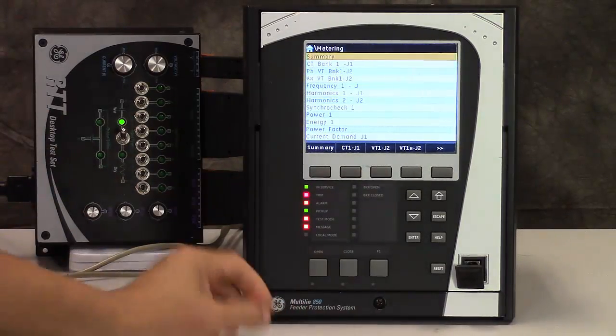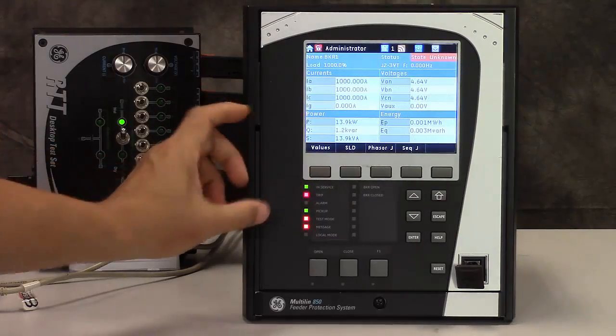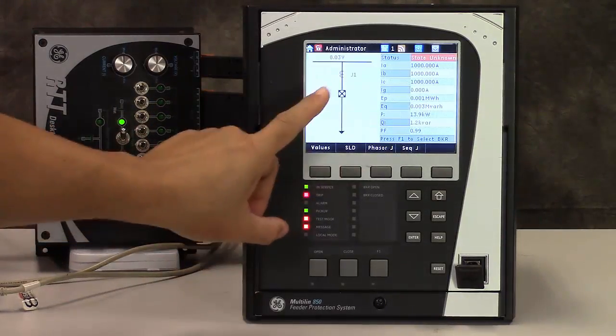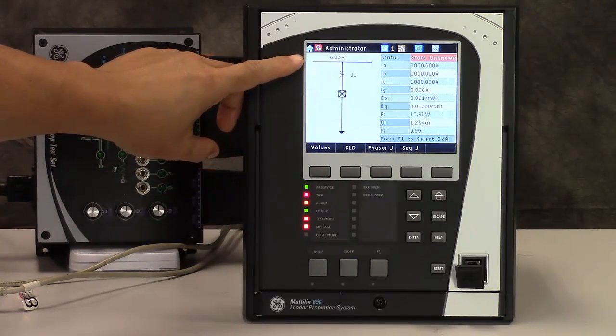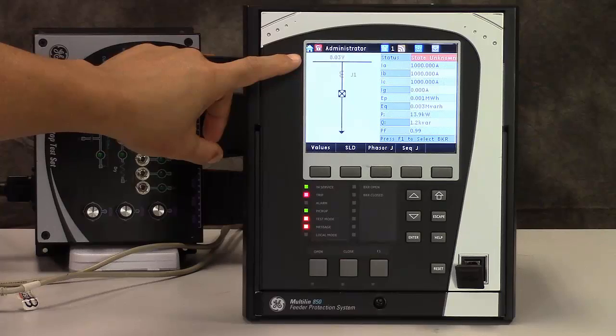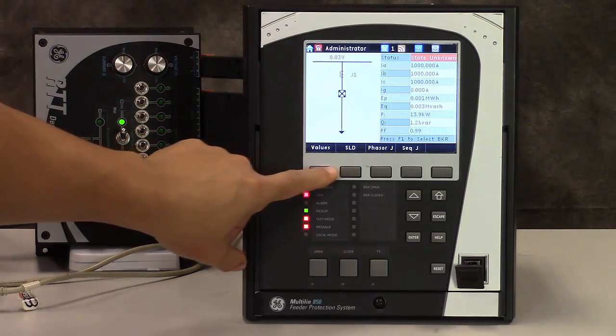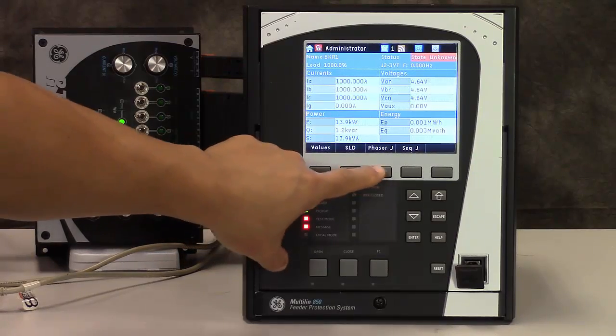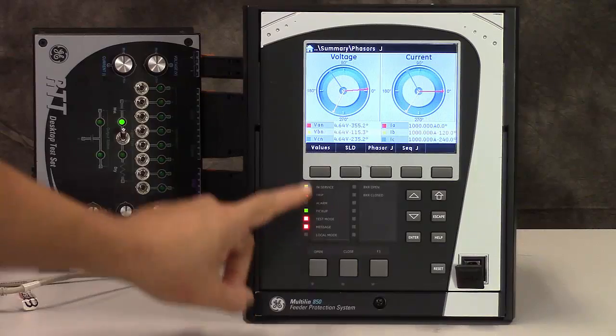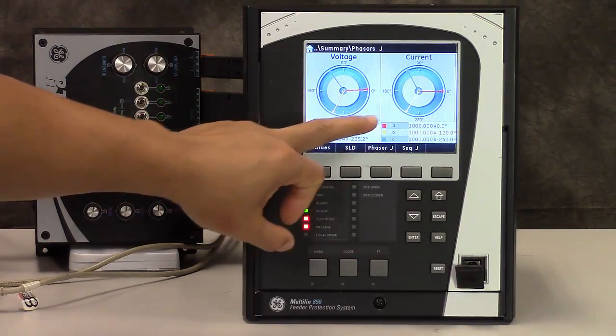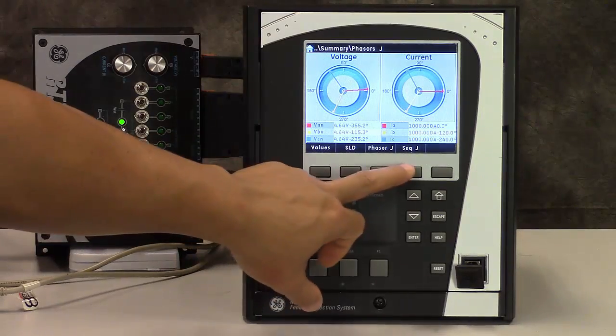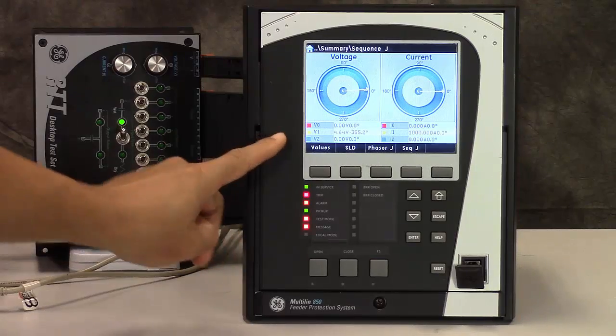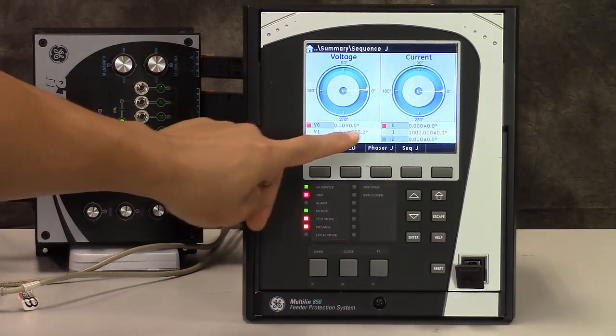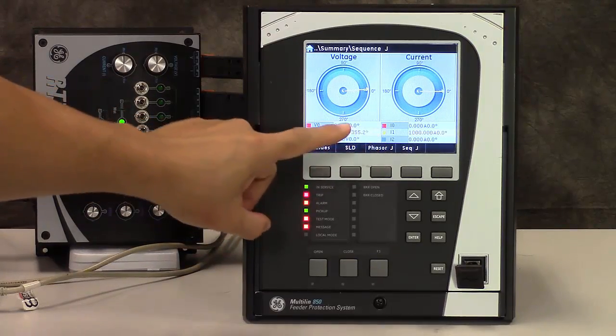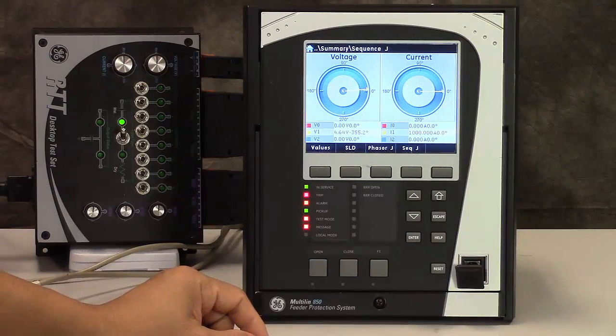From the metered screen we can see the summarized metered values of the three-phase current and voltage, or we can see the single line diagram, and the voltage shown is the average of the three-phase line-to-line voltages. And we can also see the phasors. For the phasors, we can see the phasors of the three-phase current and voltage. We can also see the positive, negative and zero sequence current and voltage, and because I'm injecting a balanced three-phase, we can see only I1 and V1, that's the positive sequence.